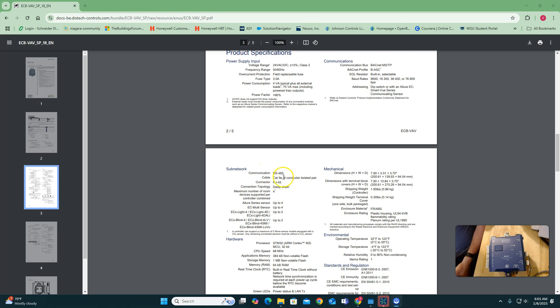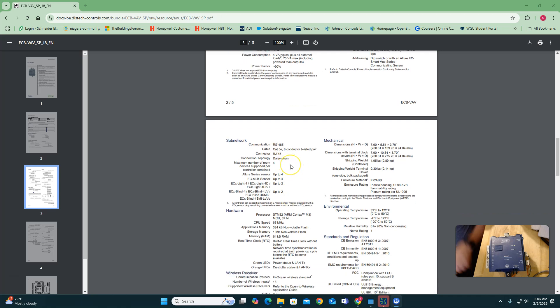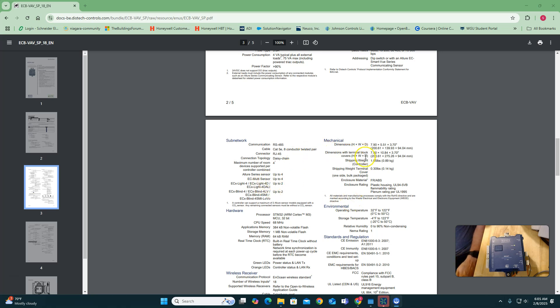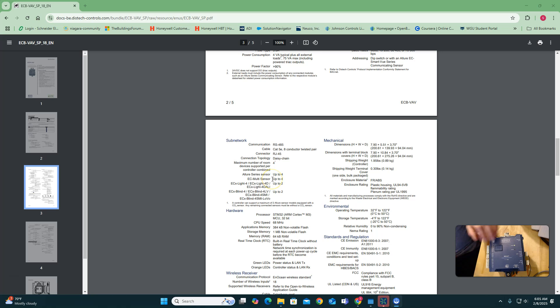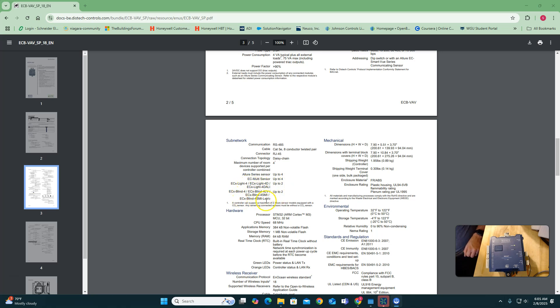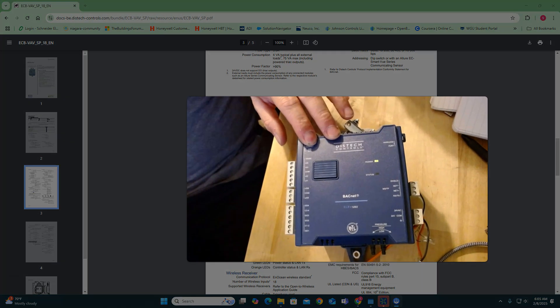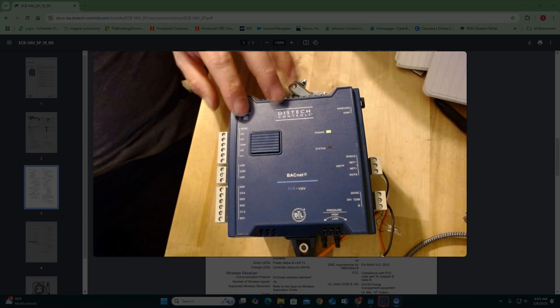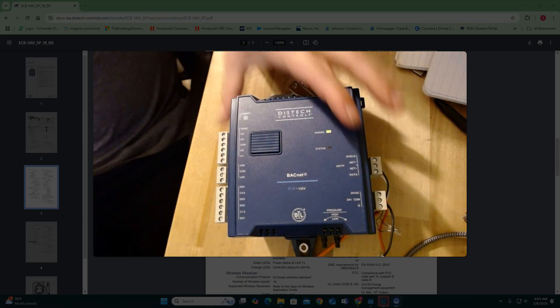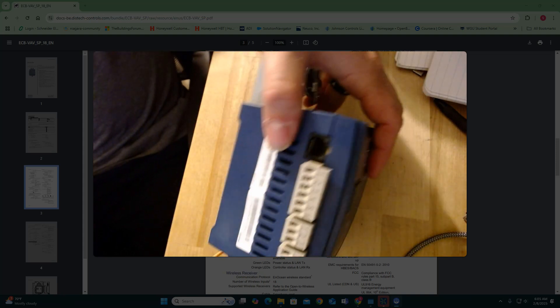The cost of these things are a lot cheaper than alternatives. So, you know, you can work with a lot here. Communications RS-485, like I said, these do come in IP varieties as well. Just a different part number. You can have, if you do the cat5 sensors, the lower sensors, you can have up to four of those guys on there. Up to two of these lighting controllers and two of these blind controllers, if you're going to do that. And that's going to all hang off of the subnet port right here on the side, which is cat5.